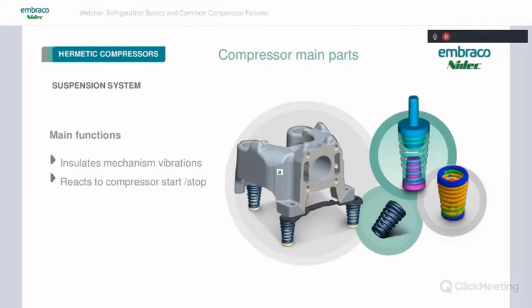So about that suspension system, basically it's there to absorb the vibrations generated from the start and stop of the compressor. Some people think it's designed to protect the compressor from shipping forces. It is not. It's only there to absorb that vibration from starts and stops.